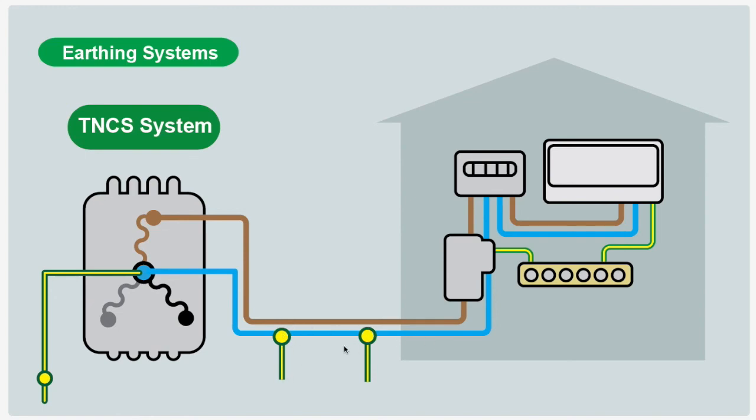the ground along the route to make sure that this neutral is earthed and limit the chance of it breaking and causing an issue where everything can rise to mains potential because of a broken neutral. So that's the TNCS system.